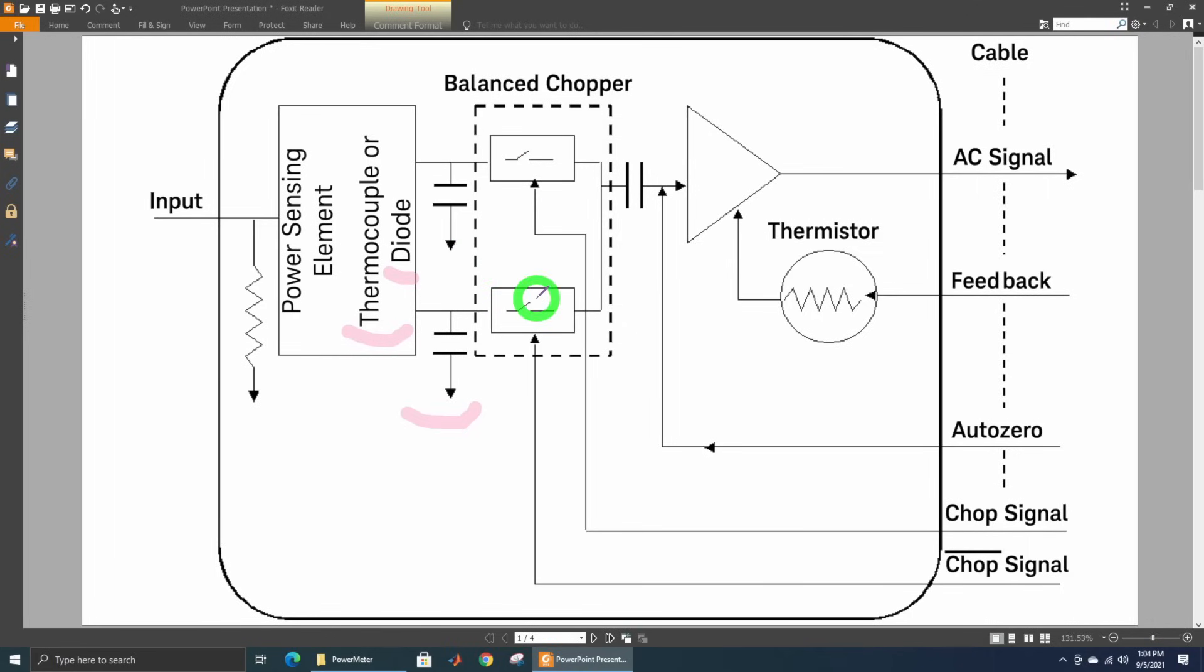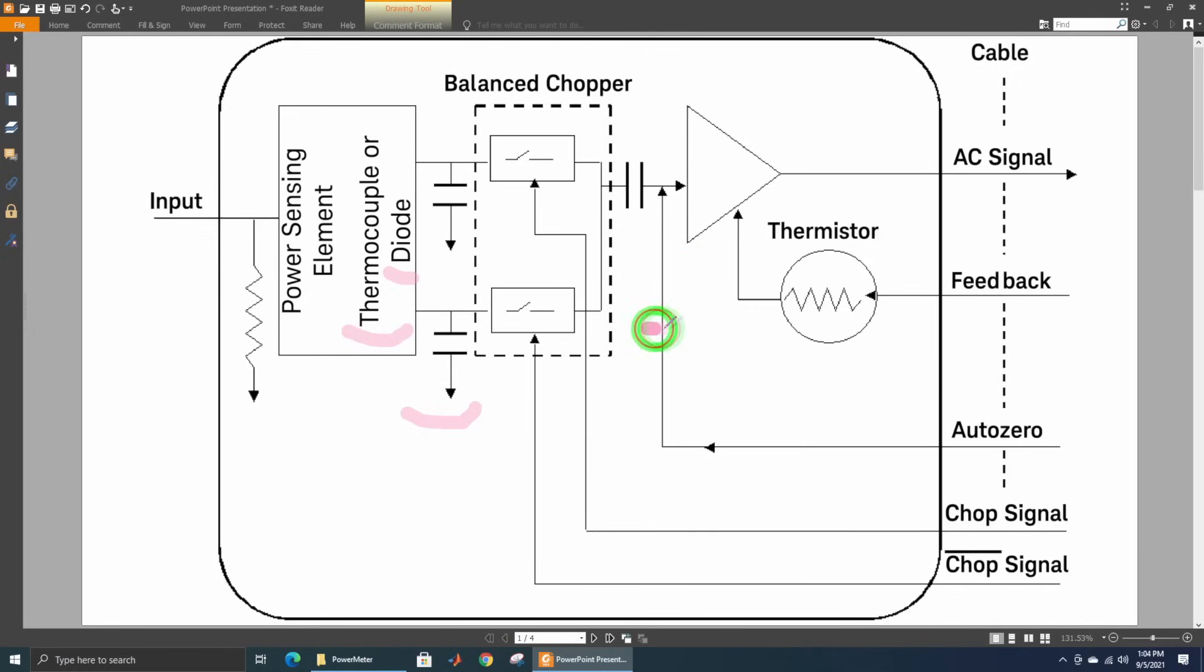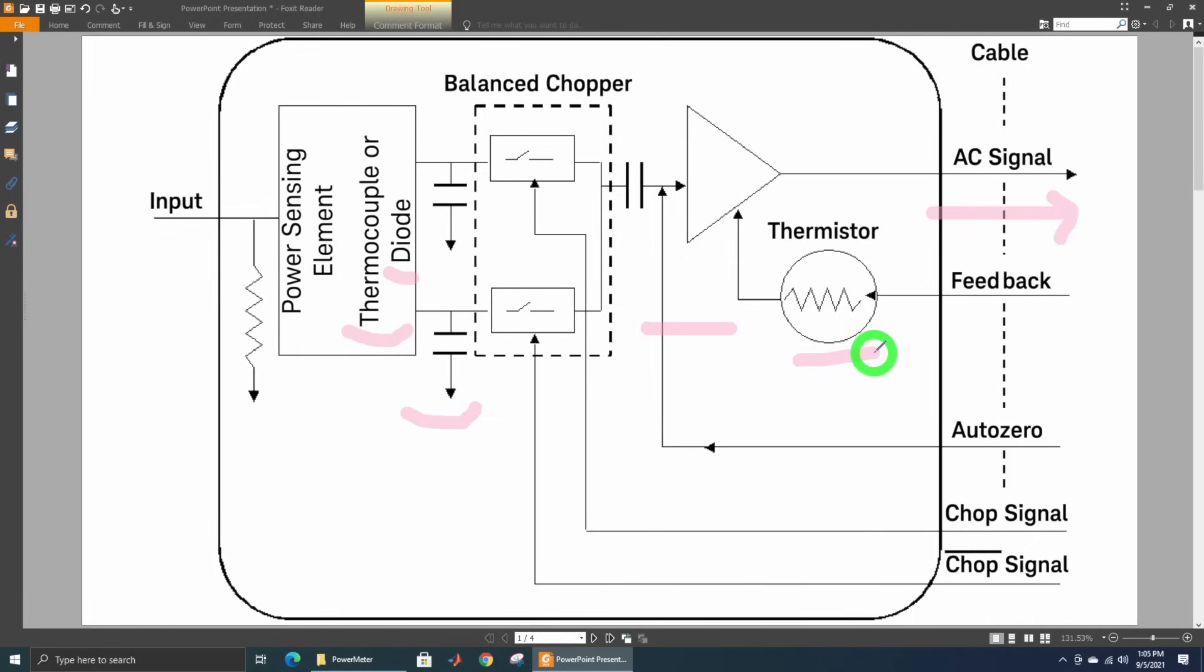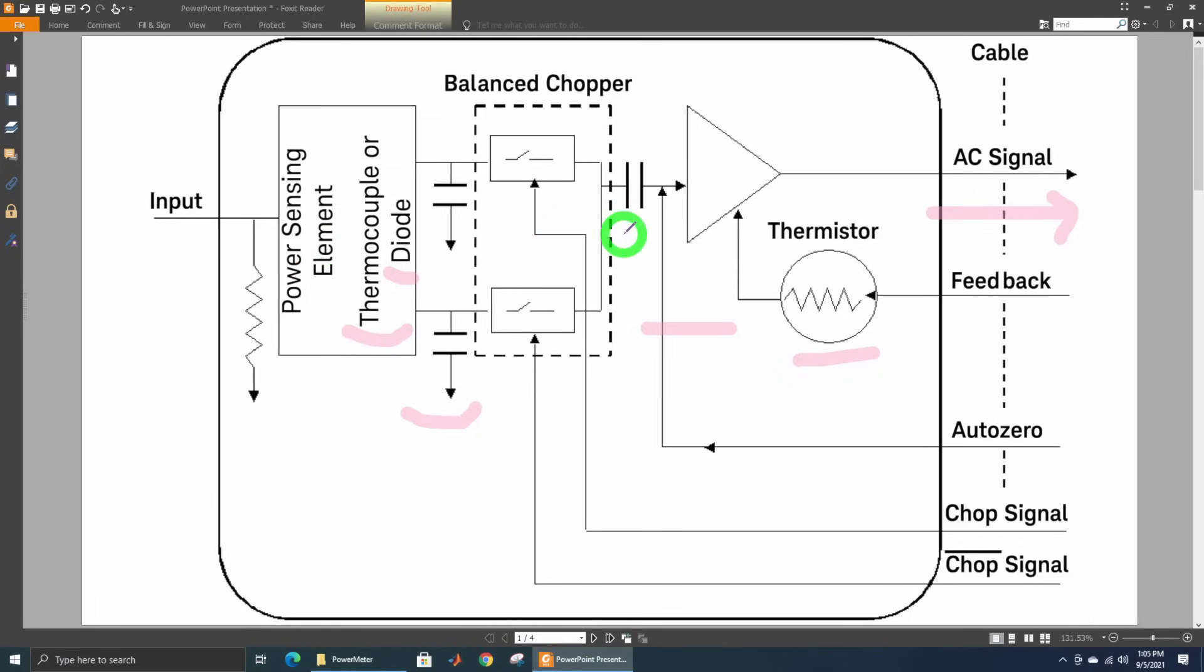Then you can have a chopper. This chopper allows you to eliminate some of the environmental effects and offsets. This is normal chopper behavior used in these amplifiers. What this does is remove the signal from being DC into some AC signal, a couple hundred hertz. Then you pass that into some external digitizer allowing you to measure the power coming in. You can also have thermistors built in to account for variation in temperature. A whole bunch of different types of calibration and auto zeroing before the AC amplifier. This technique of detecting the power, chopping it, bringing it to AC, amplifying it, and calibrating it is basically the flow of almost every power sensor on the market.